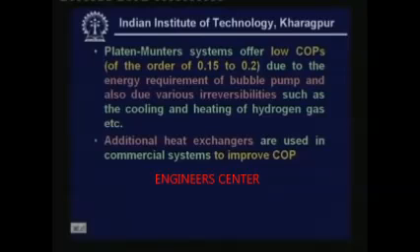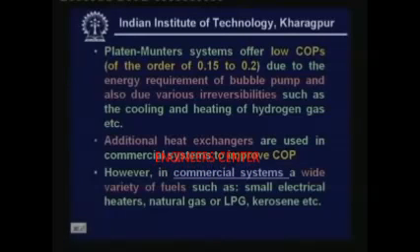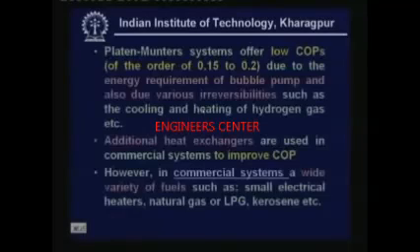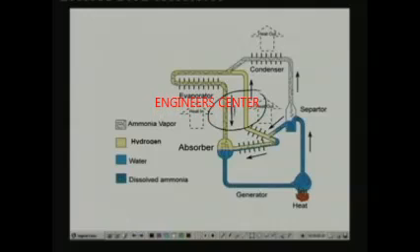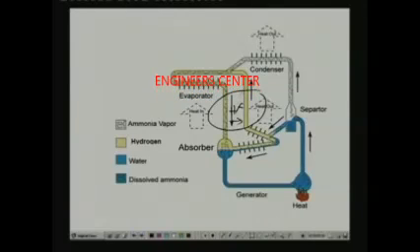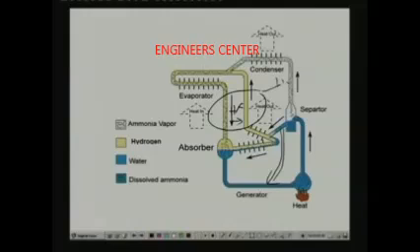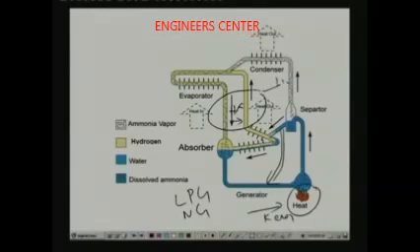Additional heat exchangers are used in commercial systems to improve COP. For example, cold vapor going to the absorber can exchange heat with hot hydrogen gas going to the evaporator, and another heat exchanger can preheat the solution going to the generator. A wide variety of fuels can be used as the heat source: electrical heaters in small systems, natural gas, LPG, kerosene, hot water, or hot oil.